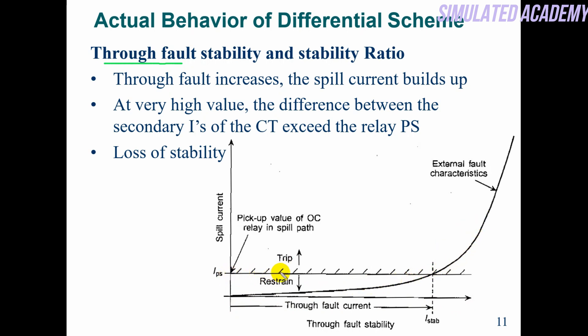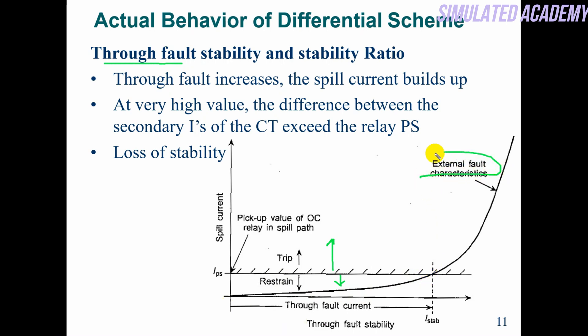As the external fault value increases, there is a minimum value called i pick-up — above which the relay must operate, and below which the relay remains in restrain. However, for an external fault, the relay should not operate. This is the CT limitation: as the through fault increases, the spill current builds up. At a very high value, the difference between the secondary currents of the CTs exceeds the relay plug setting — when the through fault current crosses the pick-up value, the relay operates for an external fault. This is called loss of stability.